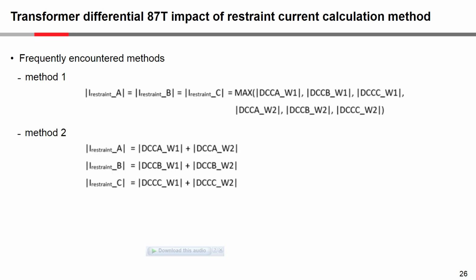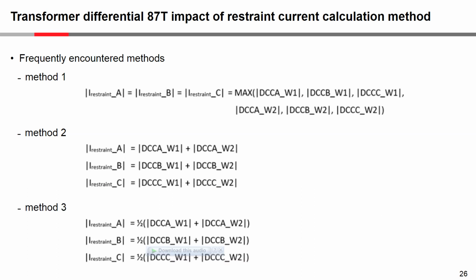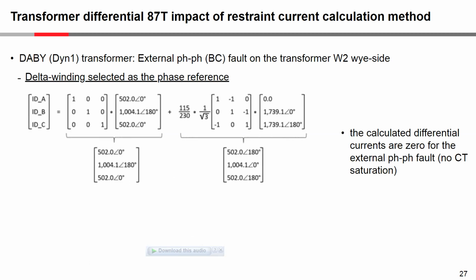Other methods would be, for instance, for phase A, to take the compensated current for phase A, winding 1 plus winding 2. For phase B, it would also be winding 1 plus winding 2, but for phase B, and similarly for phase C. And then another method may be to take the same as method 2, but have a divide by 2 factor.